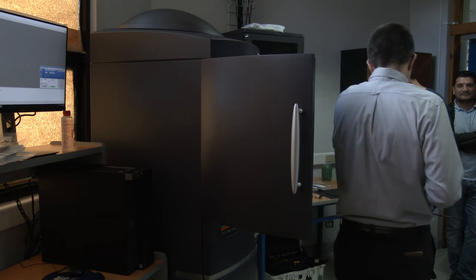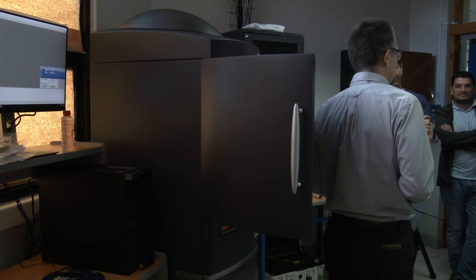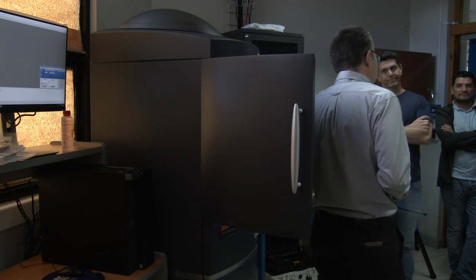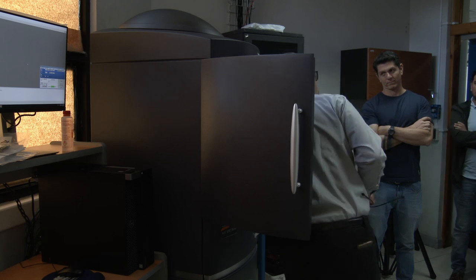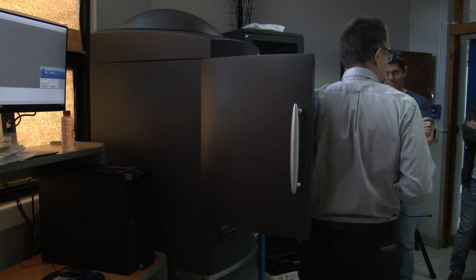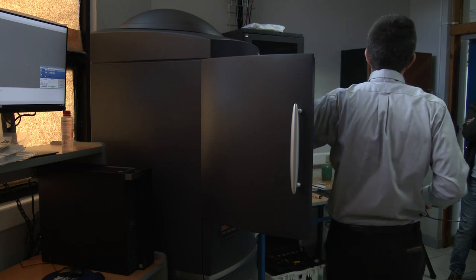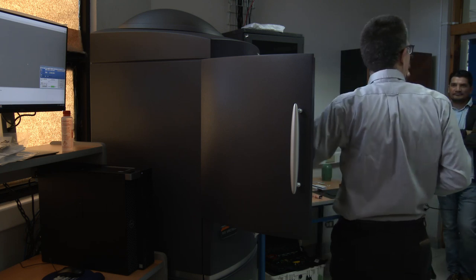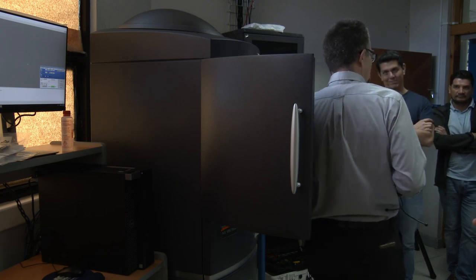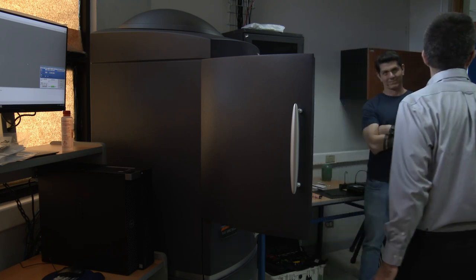If you leave the mice in here for about 90 minutes, they get thirsty. If you leave the mice in here for 4 hours, they eat each other. If you leave the mice in here for about 2 hours, they go in the side and they crawl up this lead screw. There's a spindle screw, and they go up in the top and they eat all the electronics and they defecate and urinate all over all the optics, and then I get really mad at you. Really mad at you. And we have to rewire all this stuff up top. But it takes like 4 hours to get there. And usually the beta mouse is down here and he's dead, and the alpha mouse is up here at the top. Yeah, he dies eventually too.